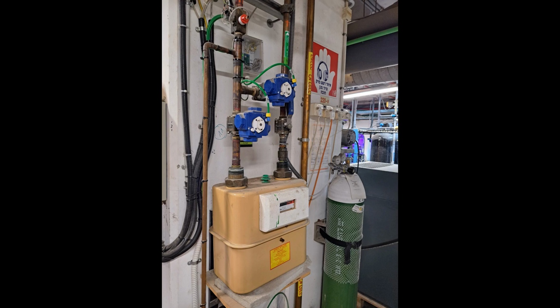In the case of the Student Lab 300 MHz NMR spectrometer, the distance is about 47 meters, so no blower or helium sacks are necessary next to the lab. However, the system should be upgraded with a PLC that controls the valves and is connected to pressure and oxygen sensors and a smart gas meter. A vent to air must be provided in case the helium is contaminated. At the Cryogenics department, a second meter and oxygen sensor needs to be installed and attached to their PLC.